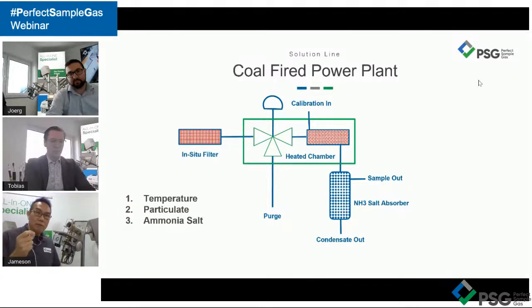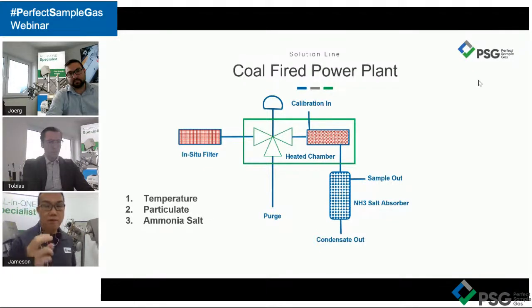The last thing that is so important is the ammonia trap, or the absorber. It is so important to have this absorber because we have to trap the ammonia salt, because the heated line is only 180 degrees. What happens if we do not trap it? At 180 degrees, it is not hot enough to contain any ammonia slip. It will actually contaminate your gas sampling system. Right over here, there is a specially designed trap for this ammonia salt before it goes to the heated line, preventing any ammonia salt from carrying over to the downstream of the sampling system.